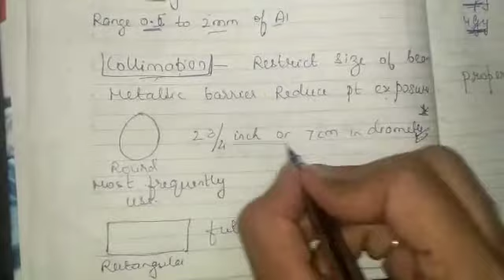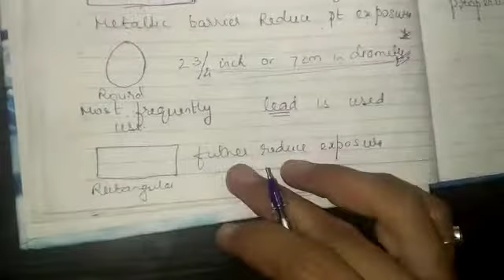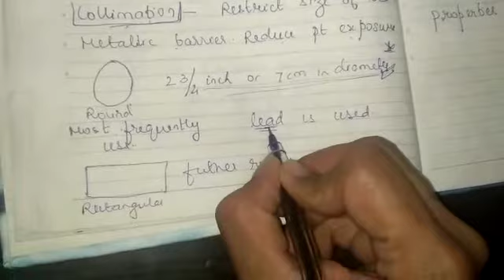Round is most frequently used, and for dental X-ray beams the collimation usually used is 2 3/4 inch or 7 centimeter diameter. These values are very important. And rectangular will further reduce the exposure. So we use lead for the collimation, and collimation will improve the image quality.